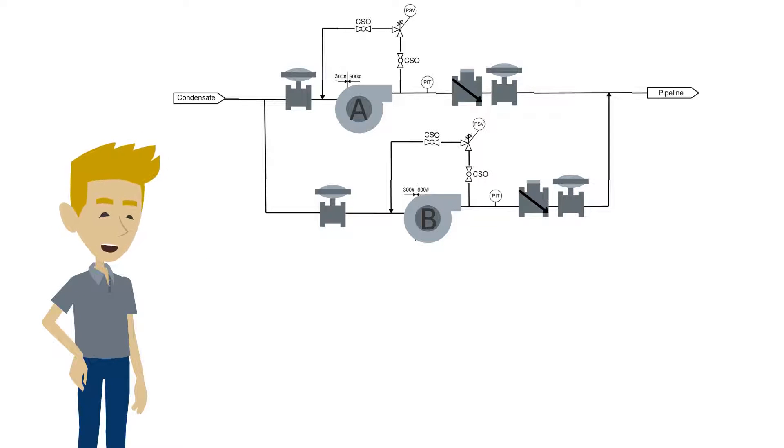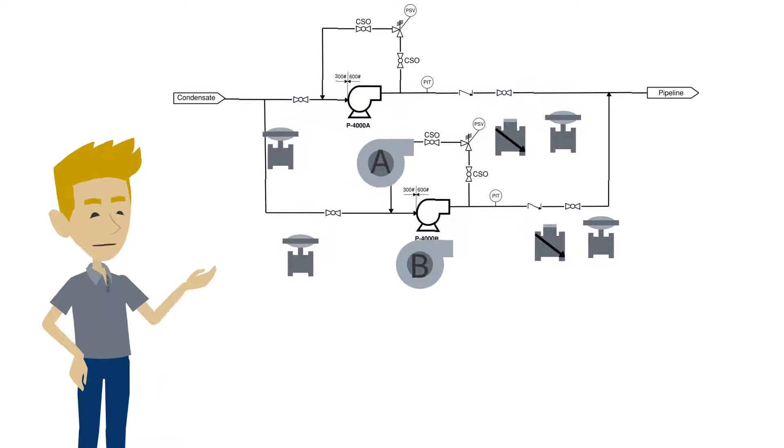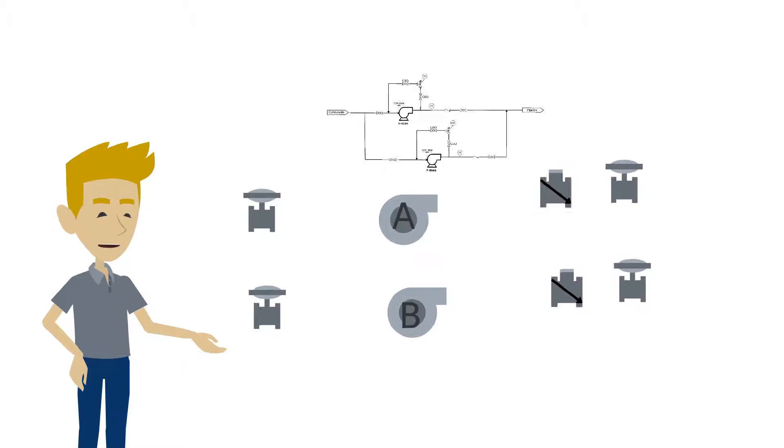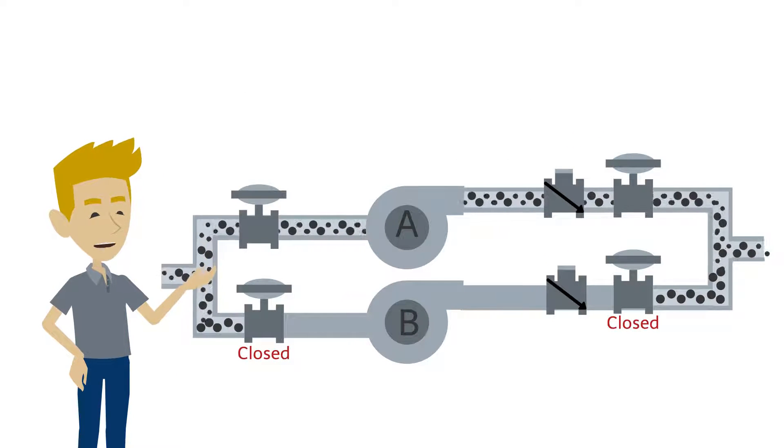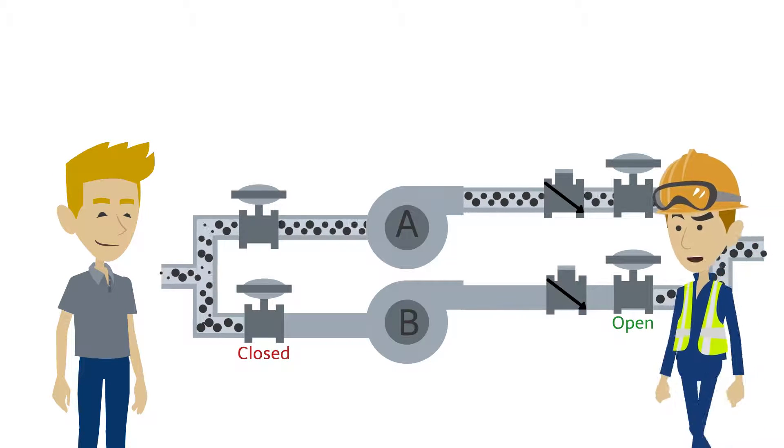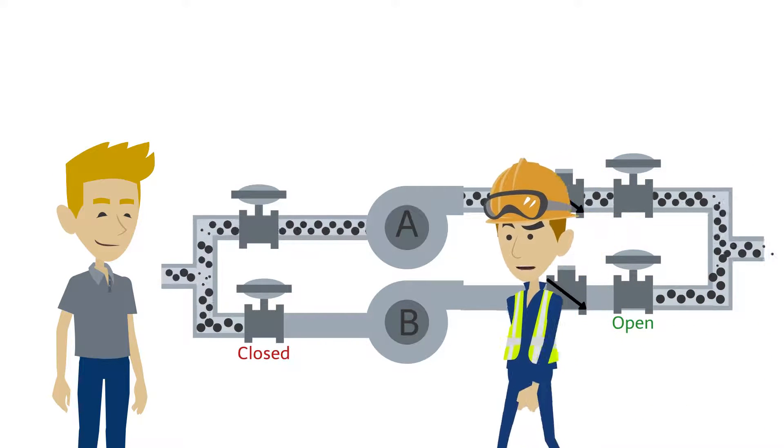With the new project to increase our production rates, we needed to turn pump B on in addition to pump A, which we have been running continuously. When you went to start up the pump, you opened the downstream valve. I had not yet opened the valve upstream of the pump when it started to leak.